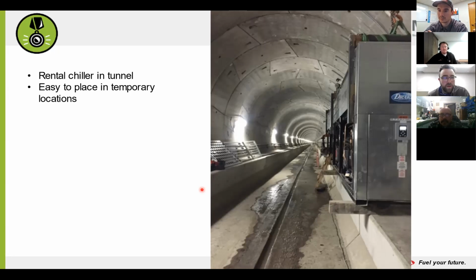So one of the common uses of rental chillers is to freeze earth. We did the same thing with the seawall replacement in Seattle down there along the piers. Froze the ground, took the seawall out, let the waves hit on the frozen earth until the new seawall could be built. Crazy. And then they yard the heat exchangers out, take the chillers away. Yep.